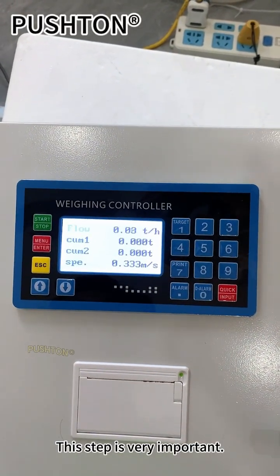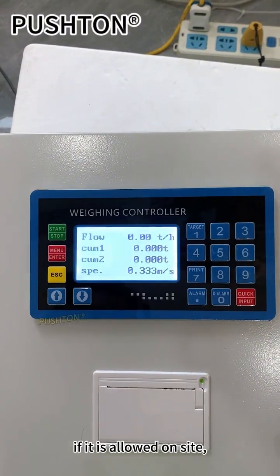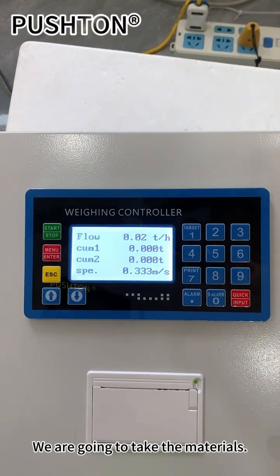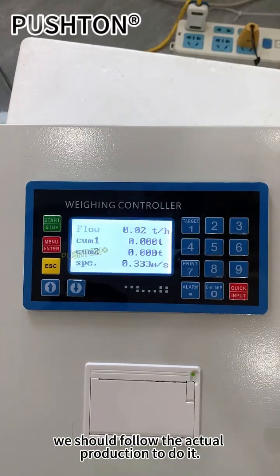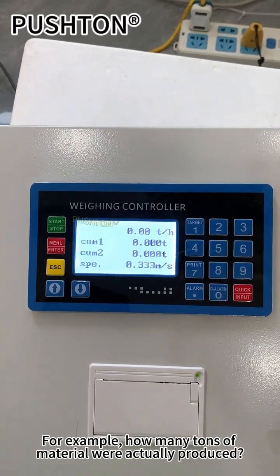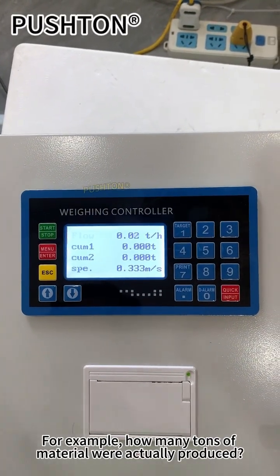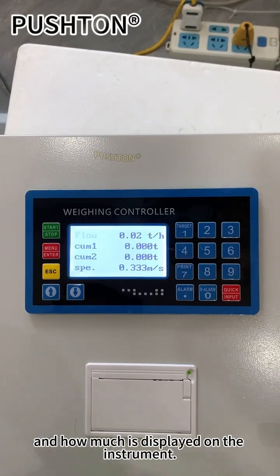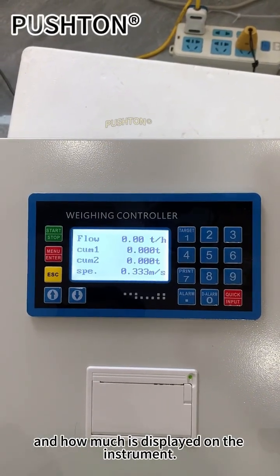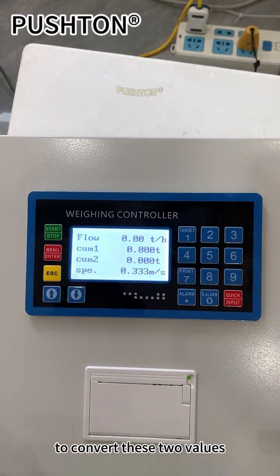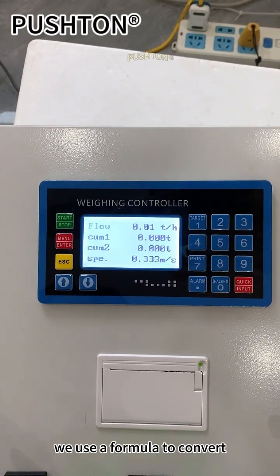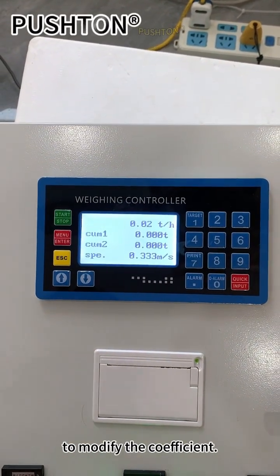The fourth step is the calibration of the range coefficient. This step is very important. If it is allowed on site, we take the materials. We should follow the actual production to do it. For example, how many tons of material were actually produced, and how much is displayed on the instrument. To convert these two values, we use a formula to modify the coefficient.